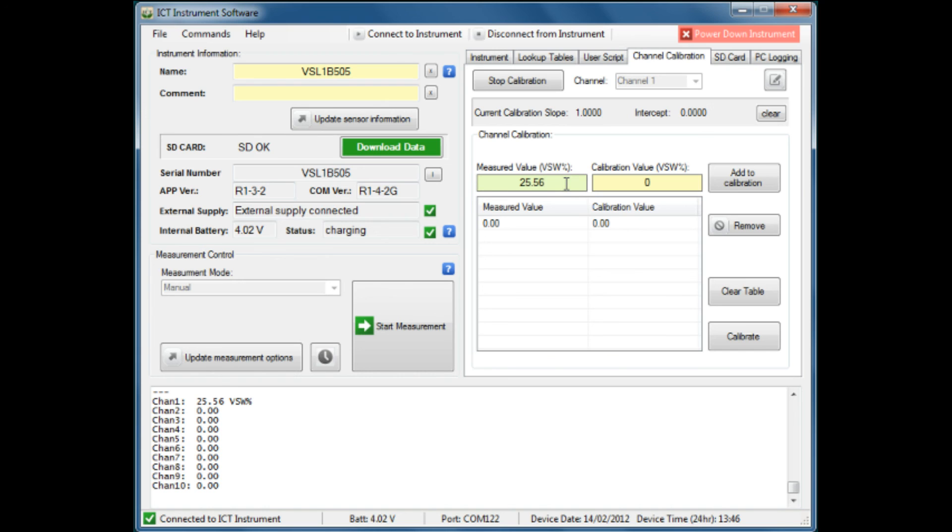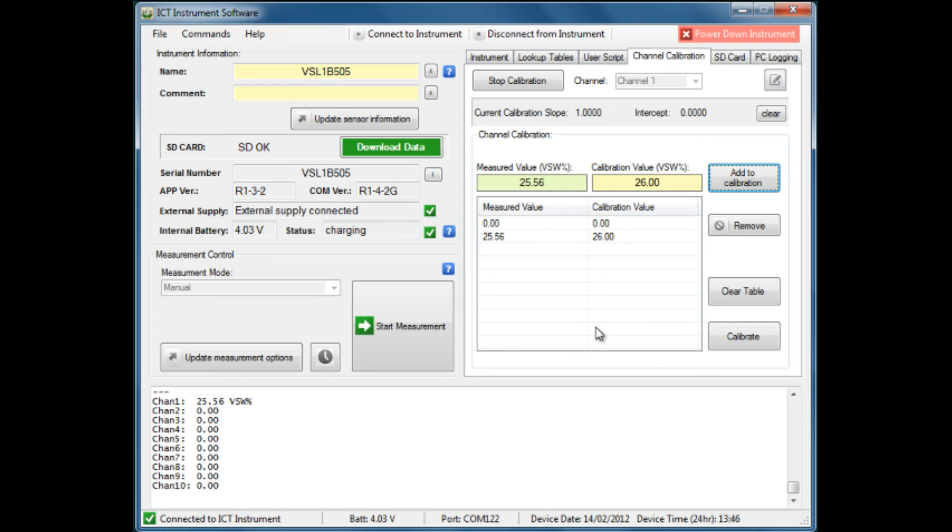In this particular case, we know that is slightly low, and the actual true value is a value of 26, which we will enter into the calibration value and add that to the calibration table. That then gives us a factor of how far away from the standard our test sensor is working.